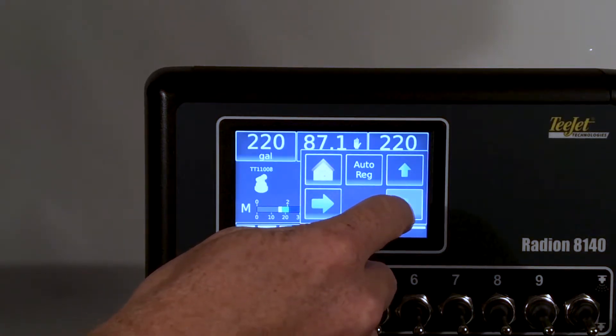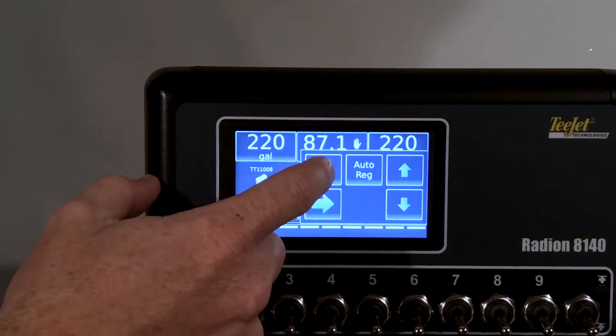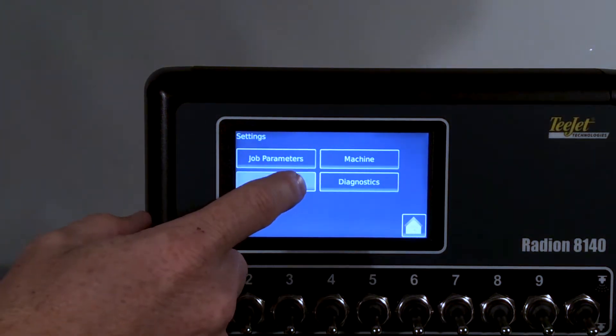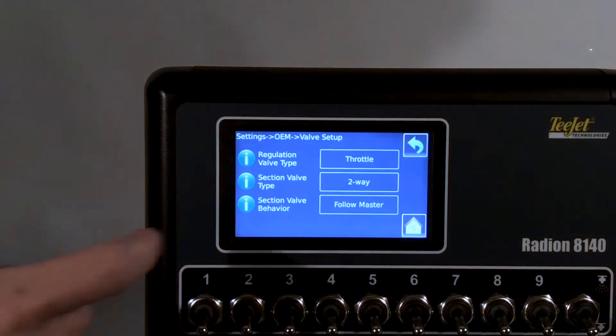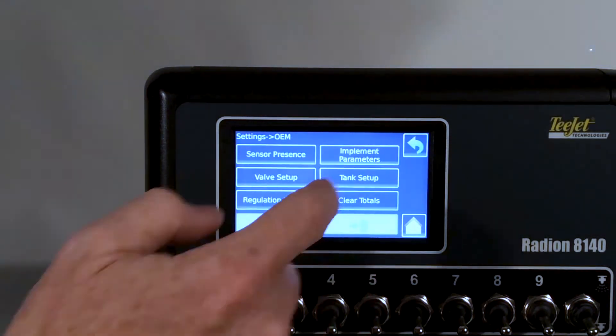Holding the down arrow should lower pressure. If that action is the opposite, return again to Setup > OEM > Valve Setup and change your choice. If it's in throttle, change to bypass. If it's in bypass, change to throttle.